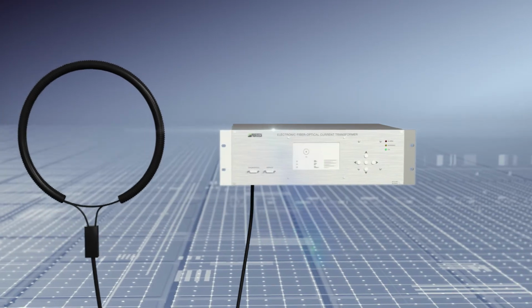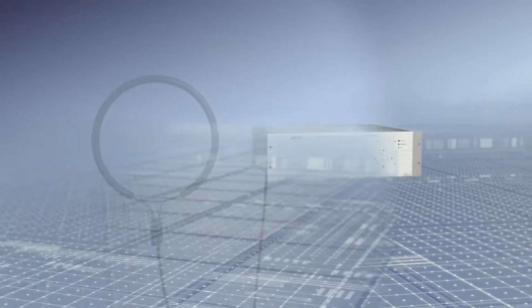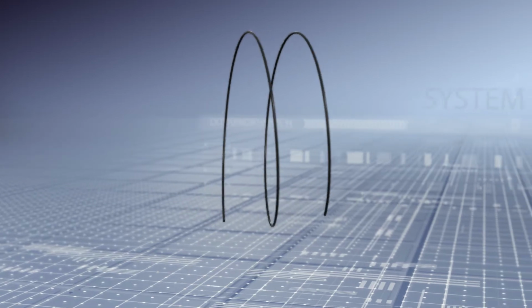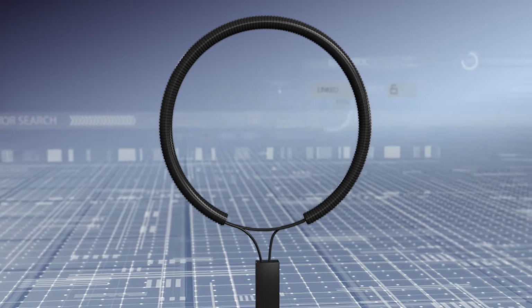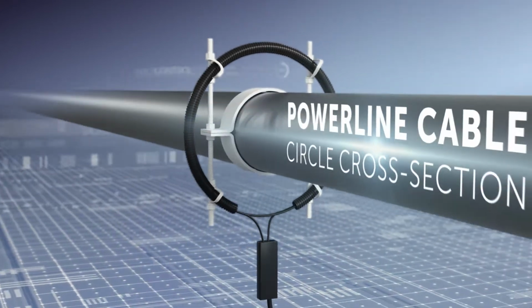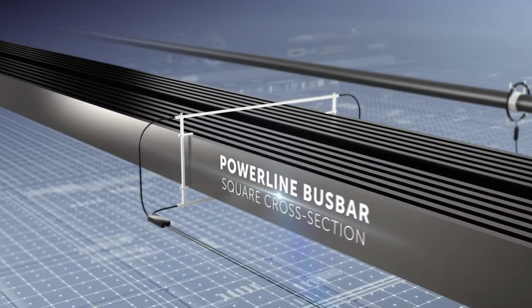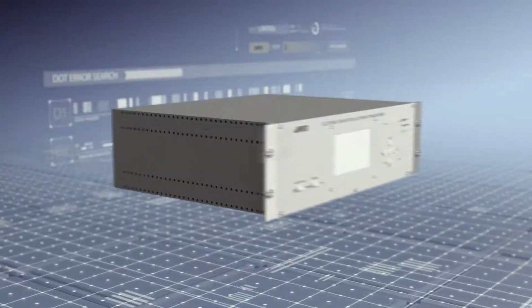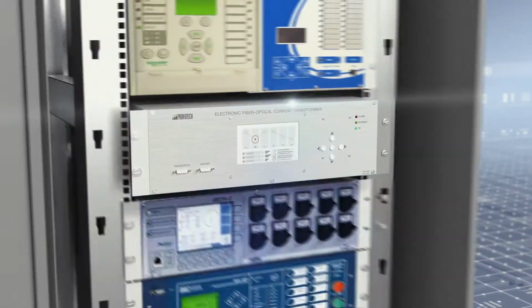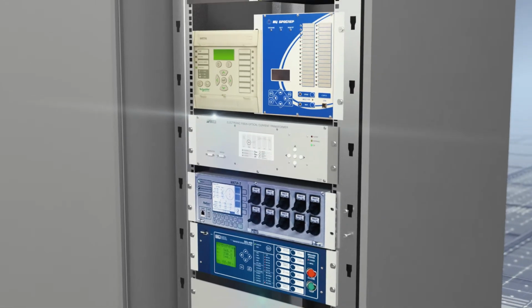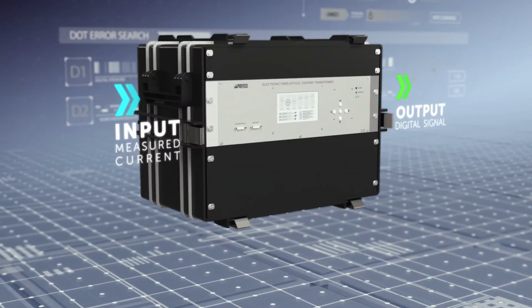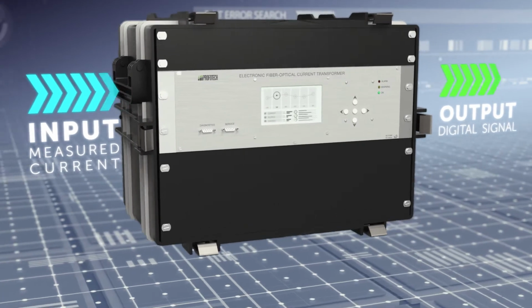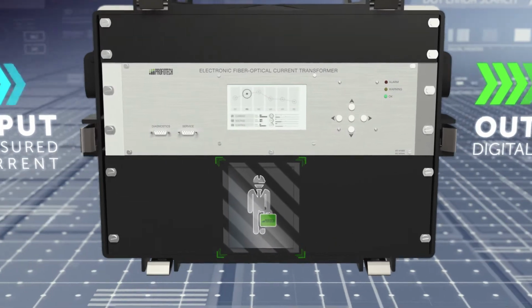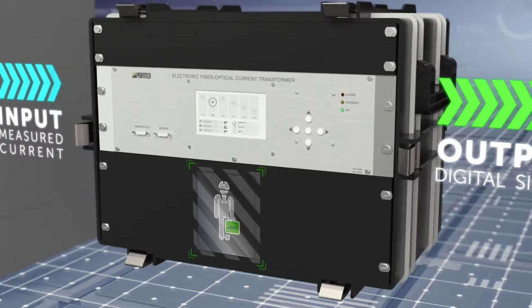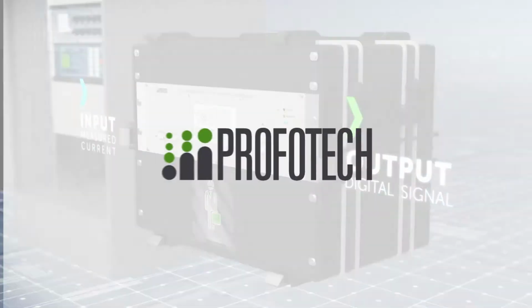Our optical flexible CT consists of two parts. A flexible measuring element is assembled from special magnetically sensing fiber optics placed in an insulating protective cover. The flexibility of the sensing element allows it to be installed around any type of bus bar. An electronic processing unit, or EPU, is mounted on a standard 19-inch rack. Our EPU can also be supplied inside a protective plastic case that provides mobility and allows extremely accurate measurements to be made directly on site.